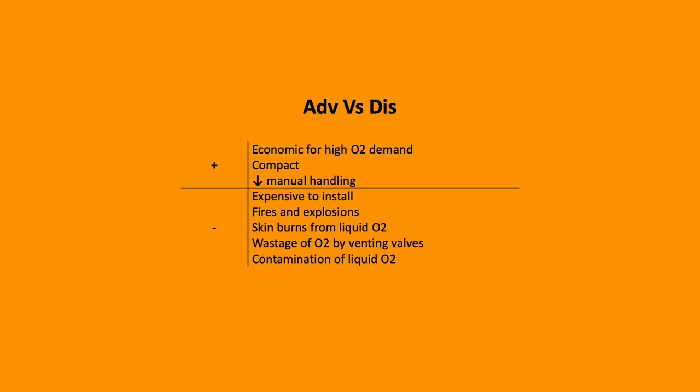Advantages and disadvantages of VIE. They're expensive to install, risk of fires and explosions, skin burns from liquid oxygen, wastage of oxygen by venting valves and contamination of liquid oxygen. However, they're economic for large institutions and in comparison to their cylinder counterparts, they're compact and require reduced manual handling.